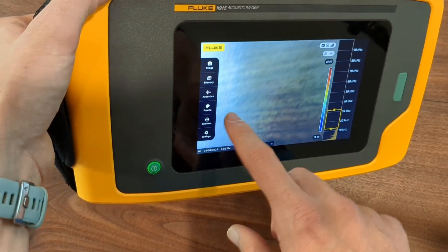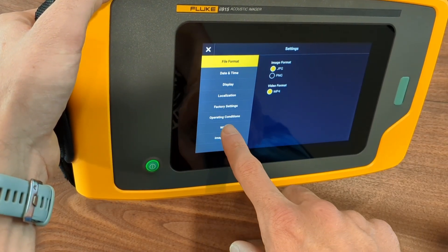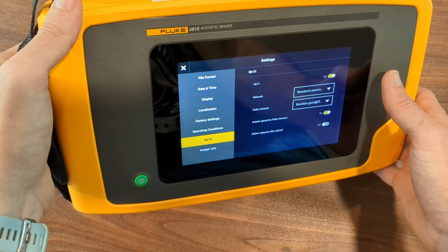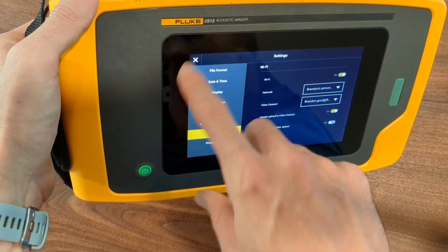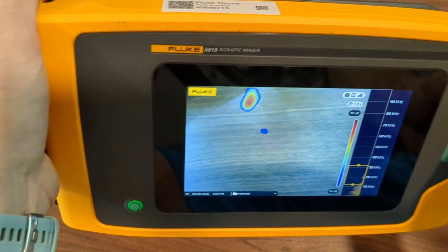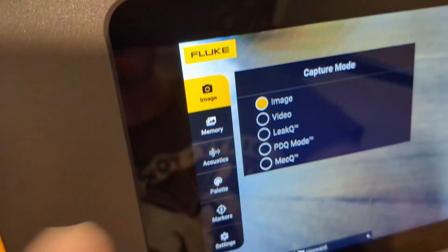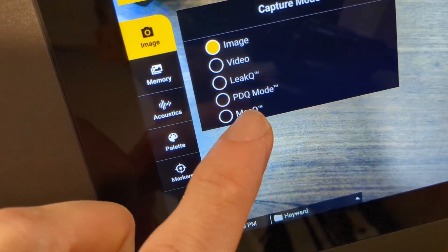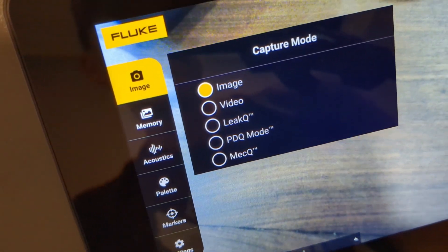I will go into more detail on how you can do that in another video and really walk you through it. But as we look at the settings, you can see this new Wi-Fi setting and it's got different options where you can connect to personal hotspots or networks. Those are the big upgrades with the ii915. They are more creature comforts than significant upgrades, but you do get all of the same features as the ii910 — your image or video LeakQ to estimate how much air leak is costing you, PDQ for partial discharge in electrical applications, and MecQ for roller bearings, conveyors, belts and things like that.